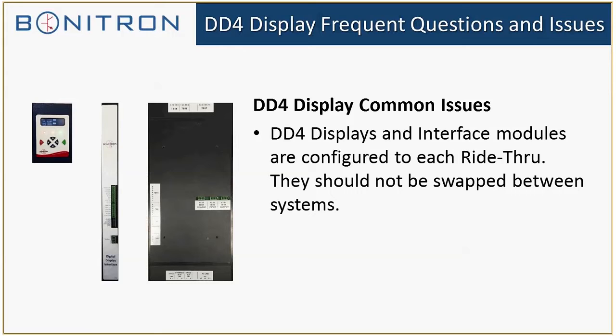But one of the optional things we have for our ride-throughs is the display. The ride-throughs were made before the display, and as a result, we had to create a separate interface card, separate from the M3460. The M3460 had already been through UL as well as CE testing, and we didn't want to modify that after the fact to add the interface board. So we provide you with a separate interface module. We call it a module, even though the board is just contained inside this plastic case. If you're going to mount it, this would be the front you'd see, and on the right hand side, if you're looking directly at this, you would see these terminal connections and these labels.